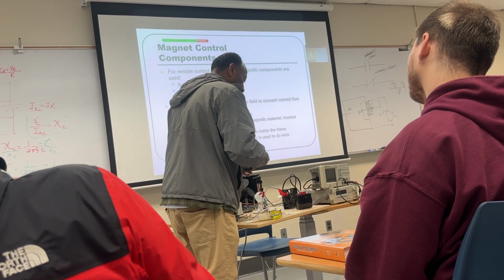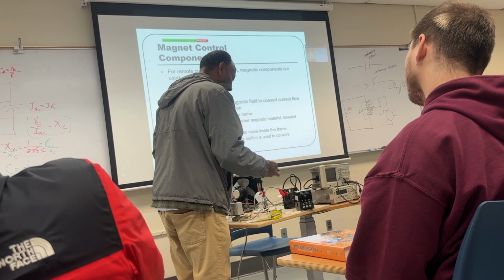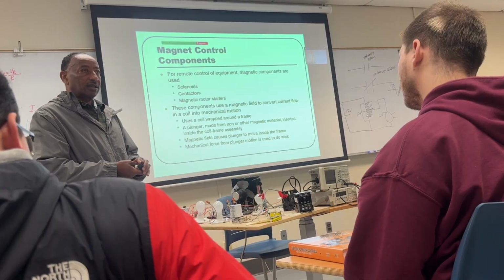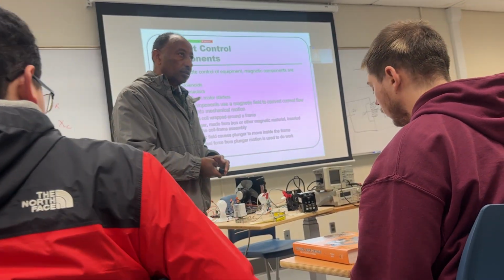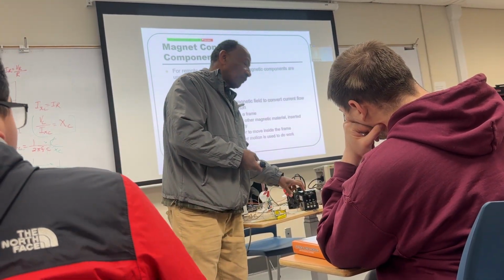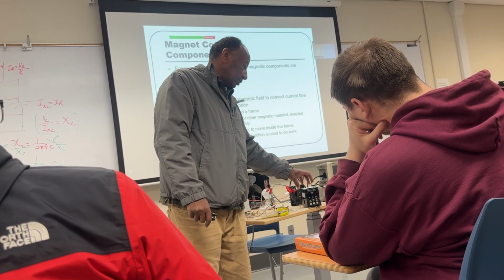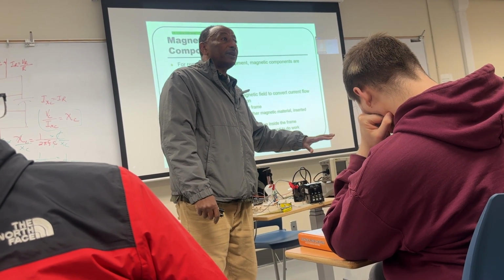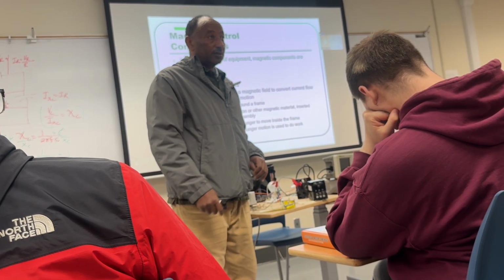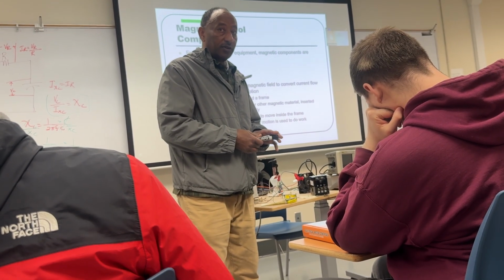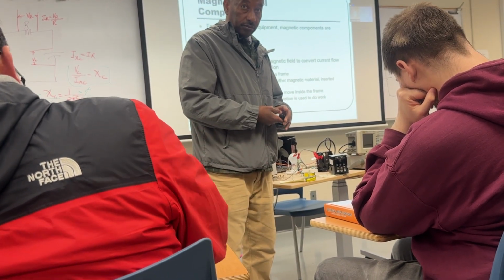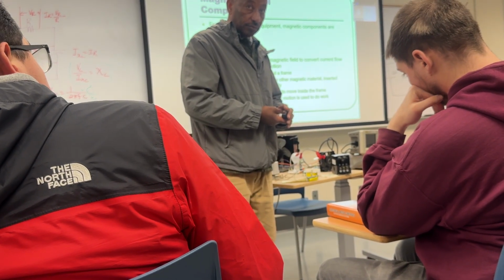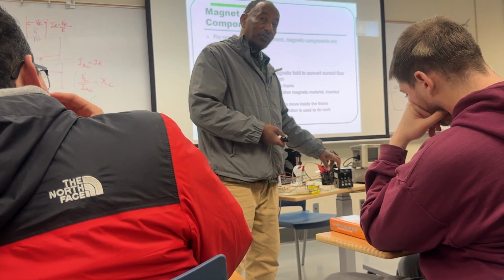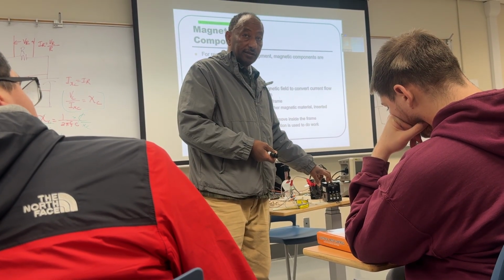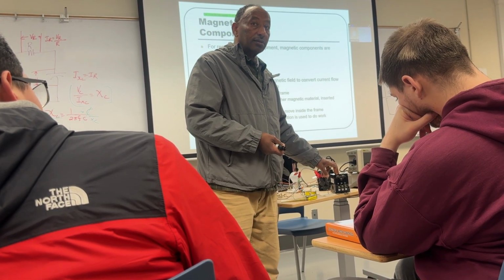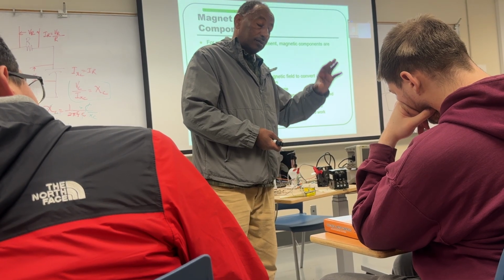But this is costly, like $200. How many volts does it take to activate it? 24 volts. There's a transformer inside that steps it down to 24. So the control circuit is at 120, and then it brings it down to 24? Yes, there's a step down transformer inside. I feed it 120, and it brings it down to 24, and that's where the magnetism works.